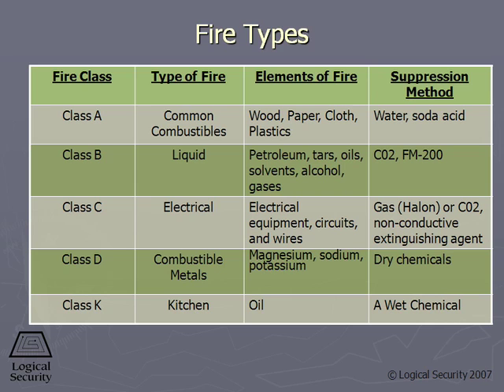With electrical fire, the first thing we want to do is shut down the power to the area of ignition. The second thing I want to do is put a gas on this as a suppressant. So again, I'll use either a halon replacement, or I'll use CO2 if I can use the CO2 in the area. Again, remember, CO2 is hazardous to humans.